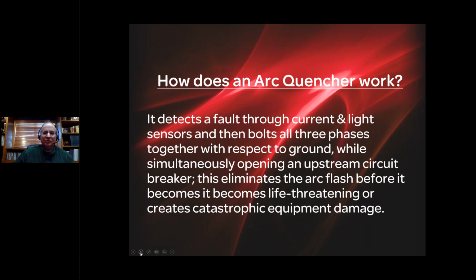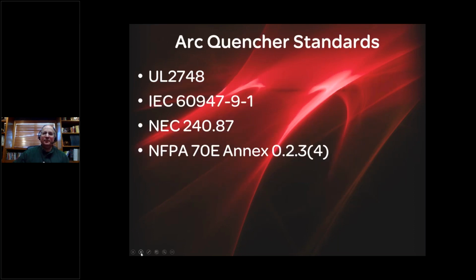So how does an arc quencher work? It detects through the protective relay. In most of our designs, if it sees more than 50,000 lux of light, at the same time it sees a rapid change in current with respect to time, it asserts the arc quencher. From arc flash initiation to complete extinguishing of the arc in a low voltage environment is less than 4 milliseconds, and less than 5 milliseconds in a medium voltage environment. And this not only provides safety, it prevents catastrophic damage to the equipment.